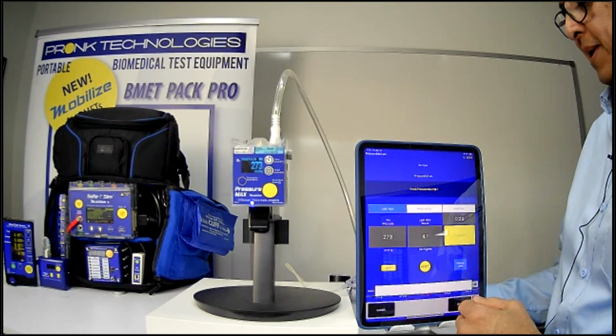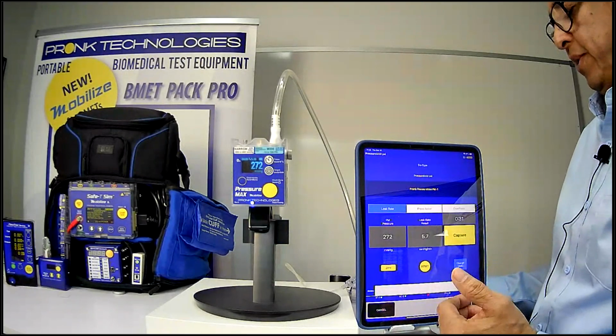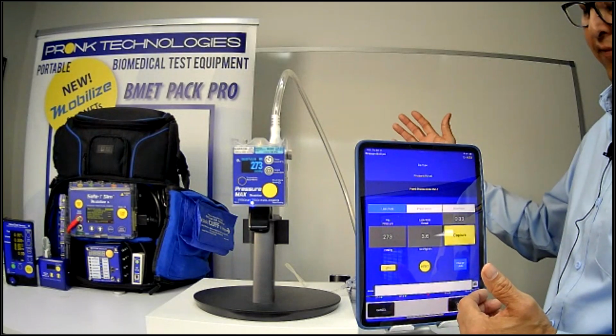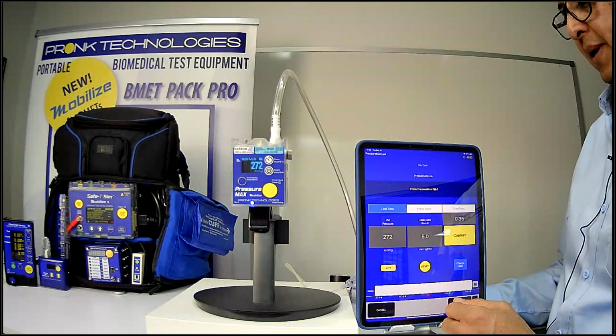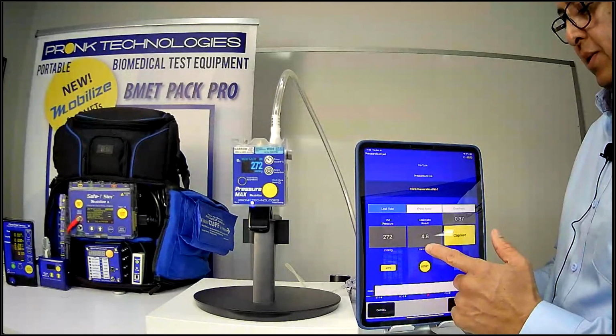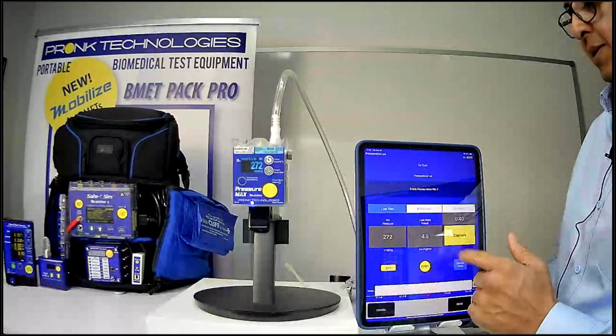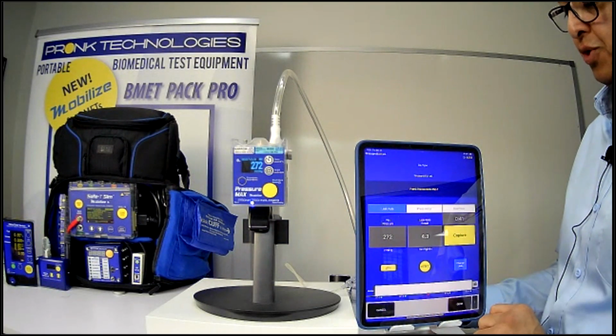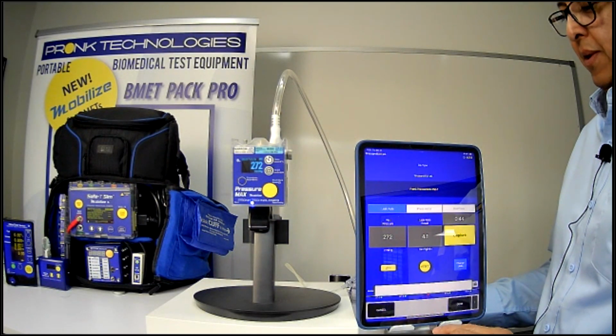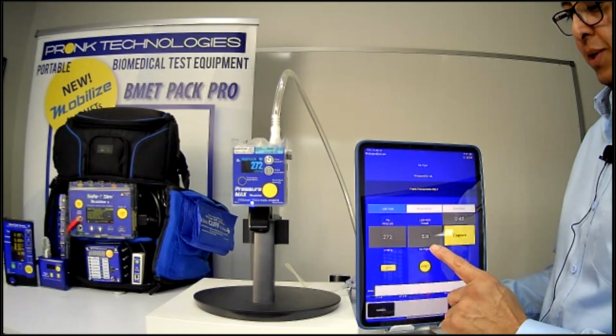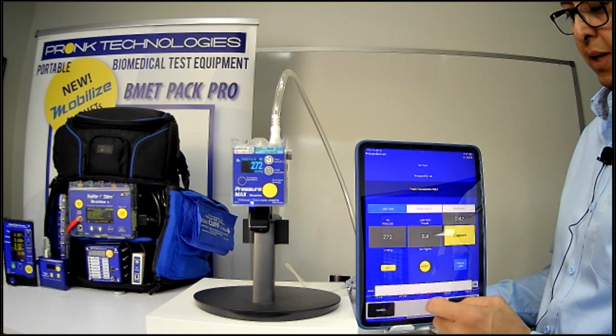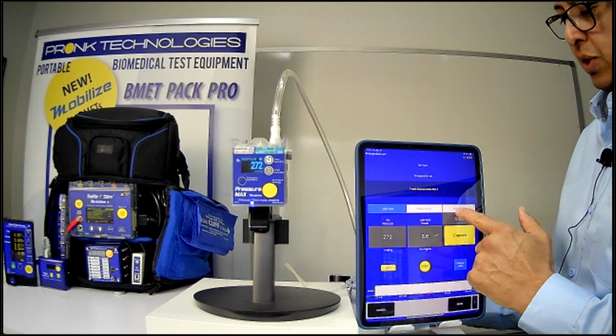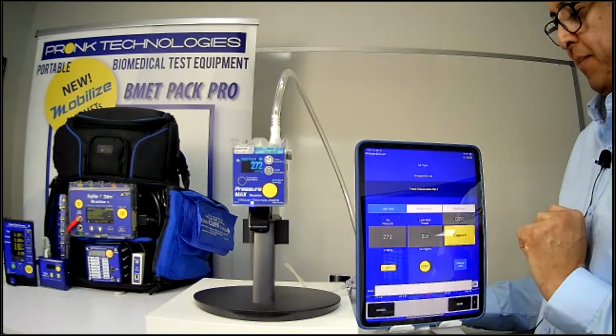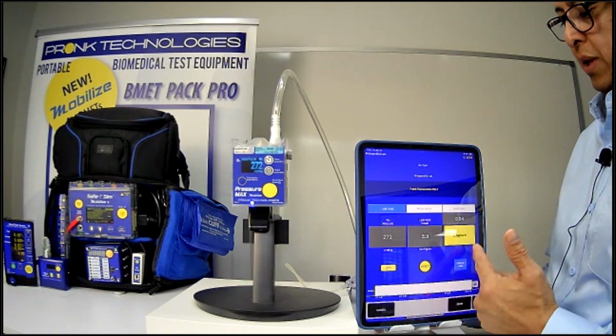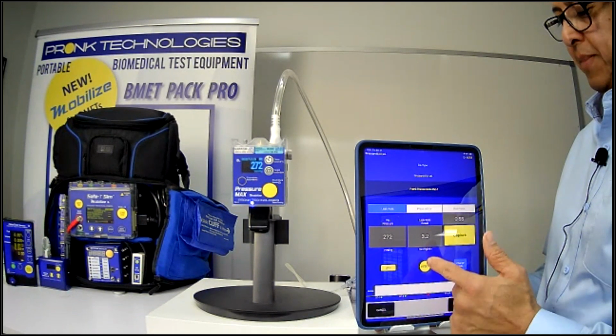You could run this time test as long as you want. You could run it for 30 seconds, a minute, up to 5-10 minutes, however long you want to run the test. The leak rate is consistently being updated as the pressure changes. I had lowered the pressure a little bit, and you could see the leak rate appeared, and the leak rate is going to start dropping because the pressure is stable, so the leak rate is reduced over the elapsed time of the test. If the pressure stays stable and time is increasing, my leak rate starts to go down.